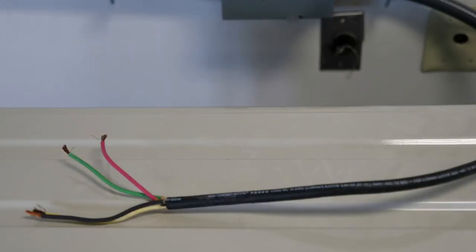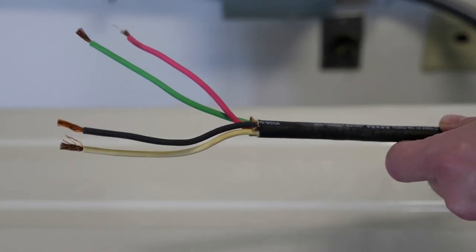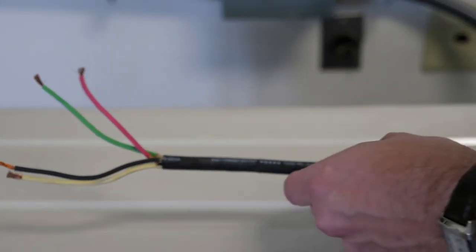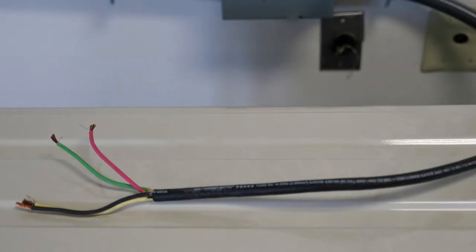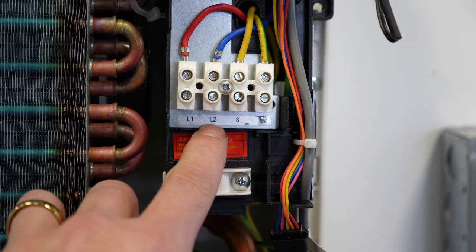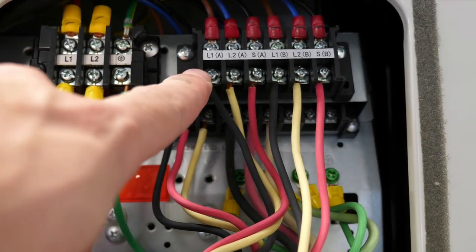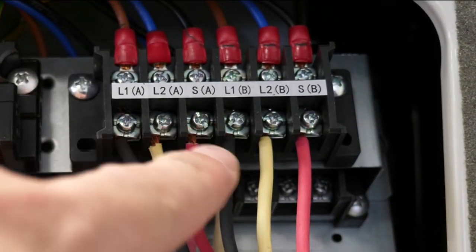The 40 MBFQ sizes 12 through 24,000 require 230-volt power and wire to a corresponding outdoor unit using a 14-gauge stranded four-conductor tray cable. This wire is landed on the L1, L2, S, and ground terminals of the indoor and outdoor equipment. This connection provides both communication and power to the indoor equipment.